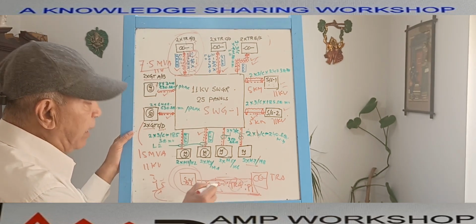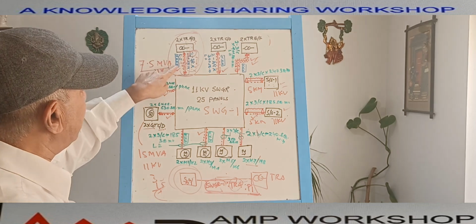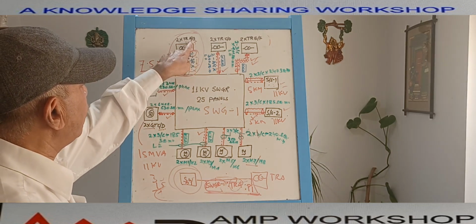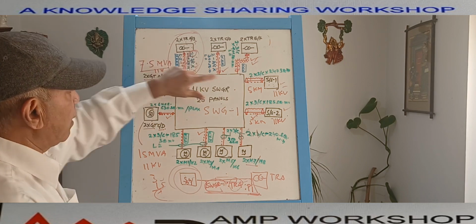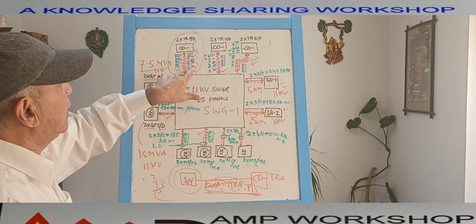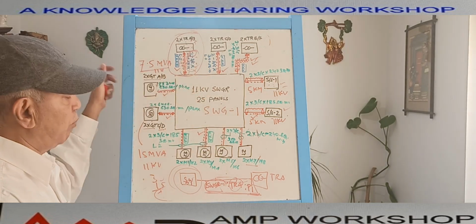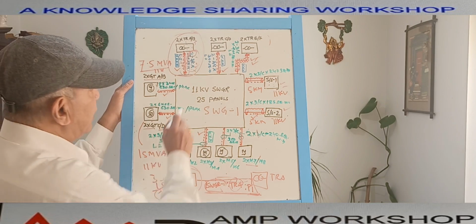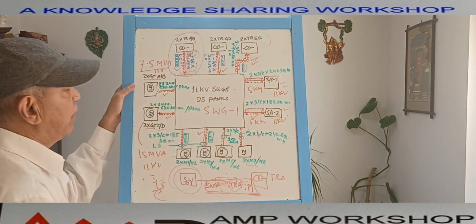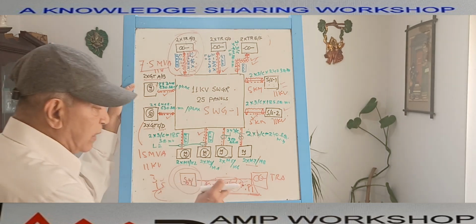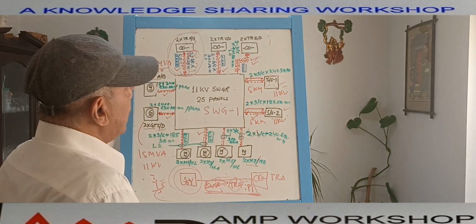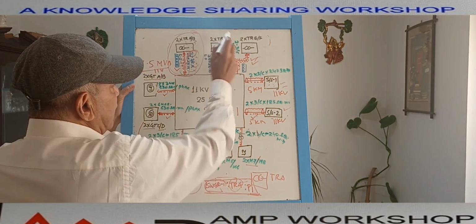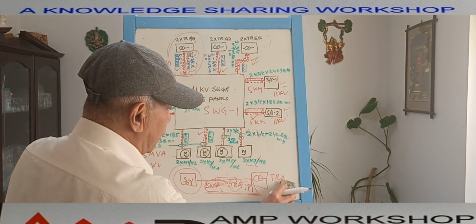This is the cable tag, and from the cable P1, when I go to the transformer I can see the cable size. It is written 1 3 core. Then I open the drawing, and I can see this cable is a 3 core 240 square millimeter cable. So these are the information I can put over this. Similarly here the same thing. Here I have two transformers, tagged C and D. So here instead of A it will be C.